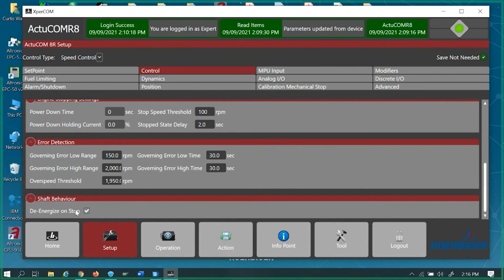Shaft behavior, you can de-energize this thing whenever it gets a fault, or you can leave it powered up. On my demo, I always de-energize it. That way I can hear it. A lot of people leave them powered up. If you're on purchased power, there's no big deal. Leave it powered up. But if you're on battery backup and stuff, I would de-energize it just to keep from running your batteries down.